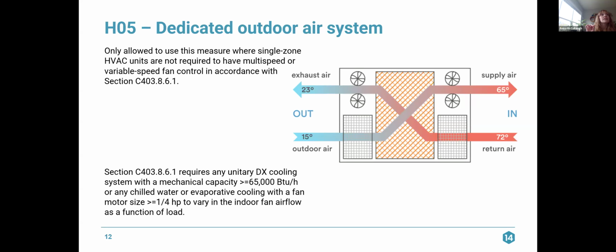So if you have, I'm sorry, I should have done this math beforehand, a 5.4 ton DX unit or greater, you have to be varying your fan speed as a function of the cooling load. And what that means is that you can't then comply, you can't use credit H05 under section C406. But if you have like VRF, or if you have fan coil units, or maybe not fan coil units, I guess if you had split DX, you could do it. But anyway, you see there are systems that you can use for compliance with this pathway.